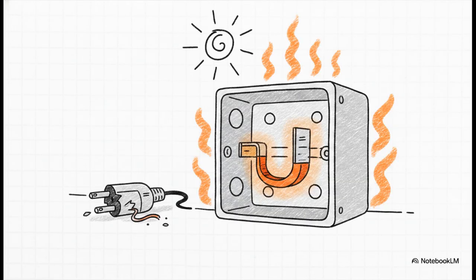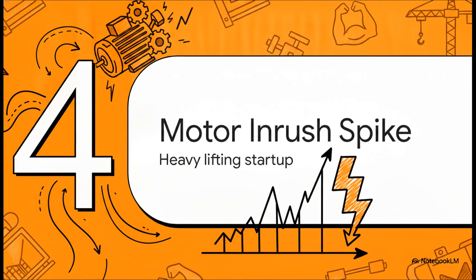This leads us to a really critical engineering reality. Breakers must often be derated when the enclosure temperature is high. Remember that slow, patient thermal bodyguard we talked about, the bimetal strip? Well, because it's sitting in that hot summer air, it's already physically heated before the electricity even begins to flow. It's starting out much closer to its trip condition, giving your entire electrical system a vastly reduced margin of safety. But wait, there is another hidden culprit causing these summer blackouts.